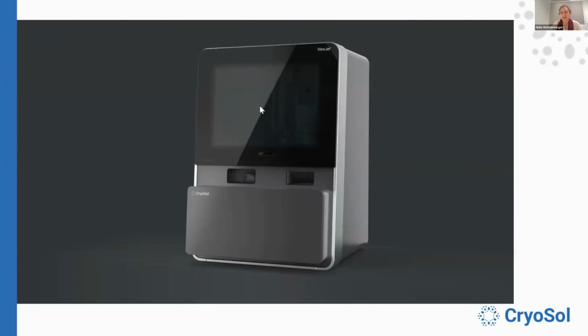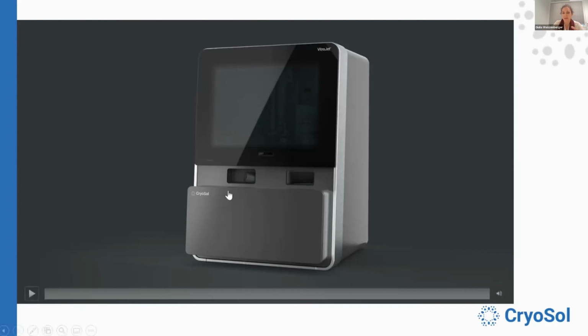Basically, we developed a machine that can be fully prepared at the start so that the user can focus on the results and on, basically, what you get from your camera images. So at the start, you see that our cryo module is actually quite large. This is because we fill enough liquid nitrogen in the cryo module, in the dewar, to keep autofill of liquid nitrogen throughout the session. And we also have an ethane line hooked up to also maintain constant levels through a number of sensors in this cryo module. We pre-clip the grids at the start of the session, and we also insert a cartridge with 12 deposition pins. So I'll show you all that.